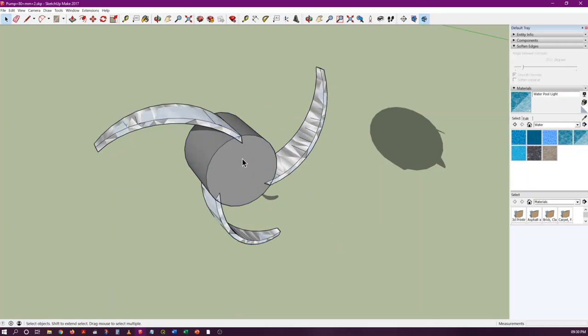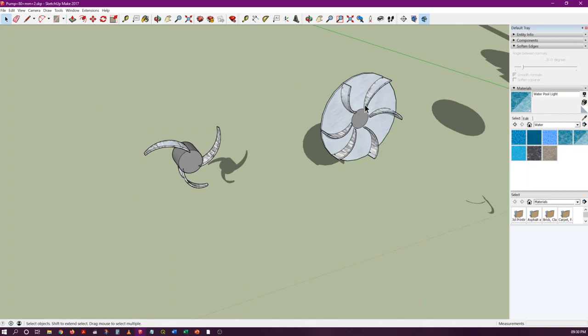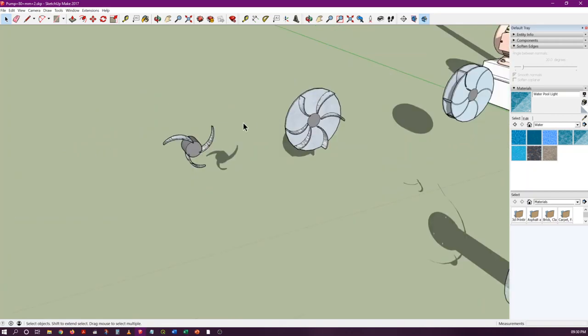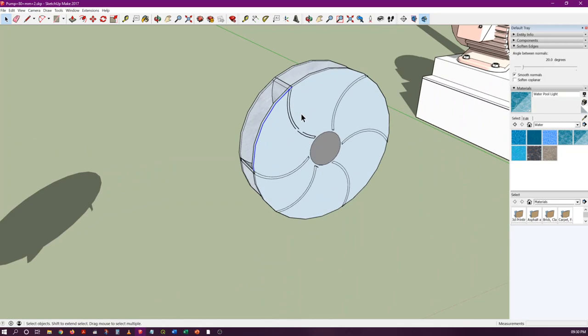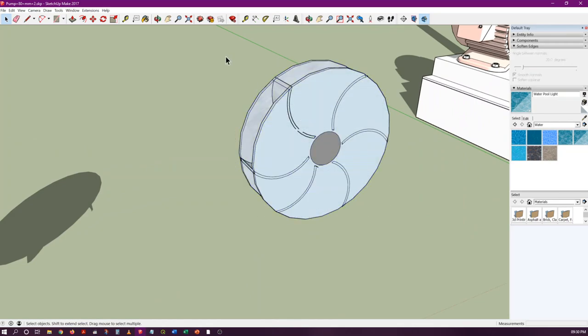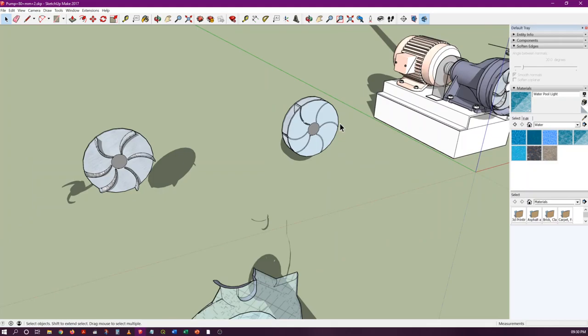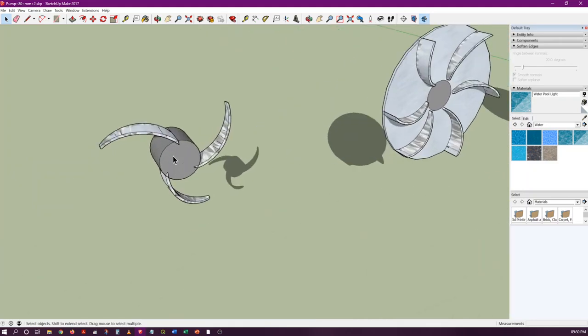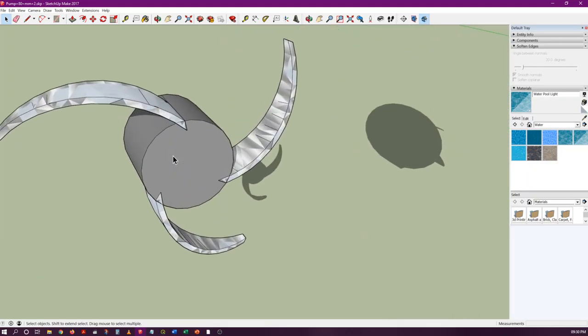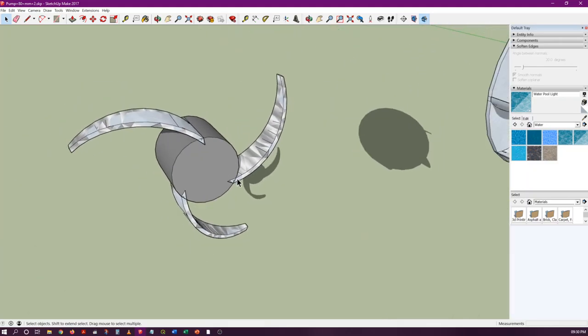In case of wastewater pumping, this kind of pump or impeller may be clogged because of solids trapped inside the casing. This kind of impeller will be much more helpful in those situations where the water has lots of impurities.